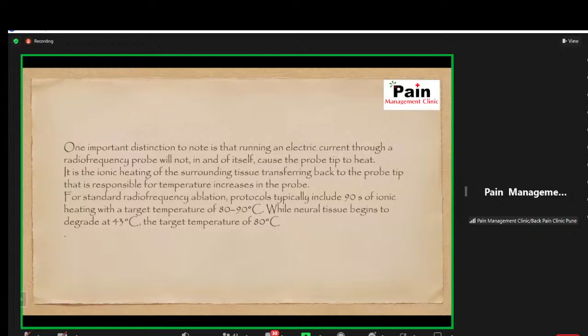So what is the difference between conventional radio frequency and cooled radio frequency? We will go into detail. The key limitation of standard radio frequency ablation is charring of the tissue, as Dr. Dhruva was telling. Even if we increase the duration, it will start charring, and whenever there is charring, that charring acts as an insulation. So the tissue beyond that lesion will not heat. Even if you increase the time, there will be charring around this lesion. That is the biggest disadvantage, limiting the size of the lesion with conventional radio frequency.